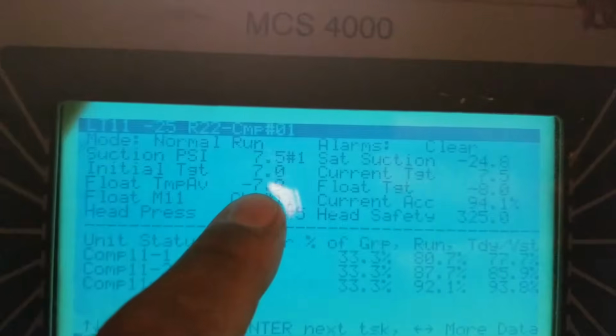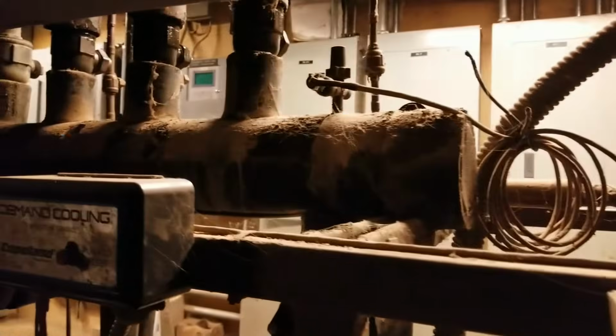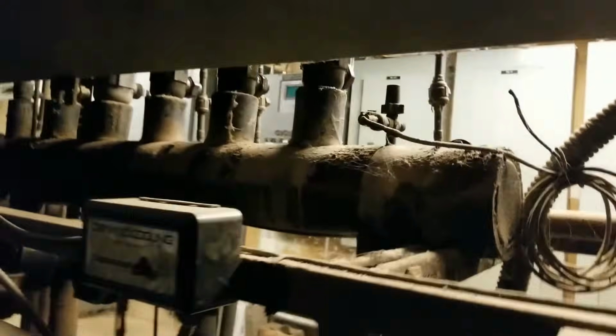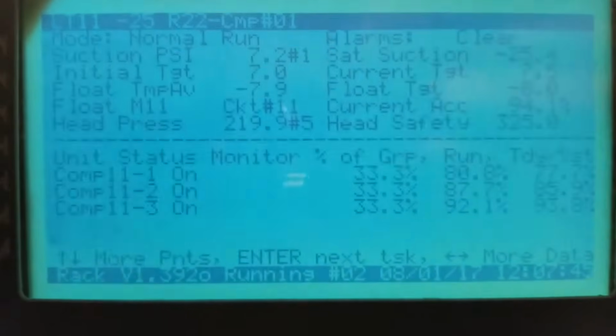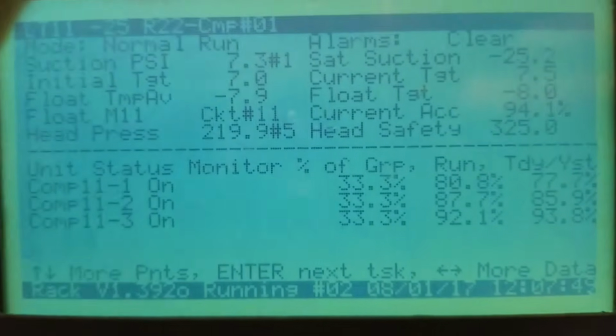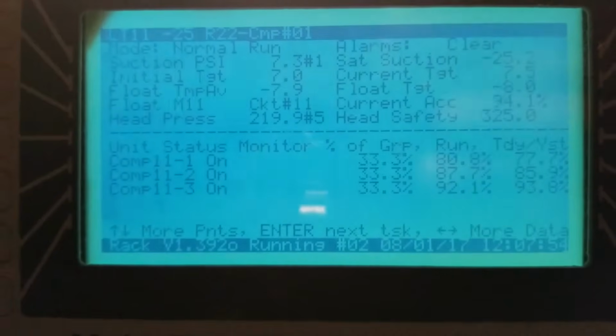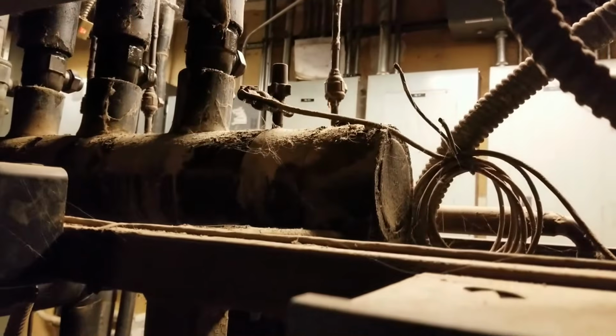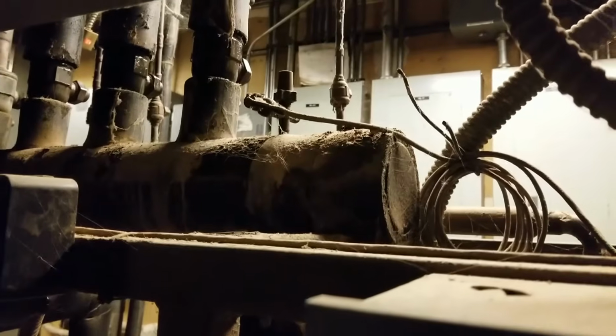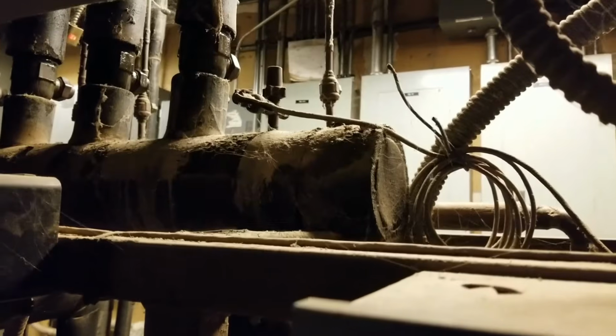So these cases do not have thermostats inside of them or an EPR inside of them. It's being controlled off the suction header, which is right here. That transducer right there is actually controlling your temperature for the frozen food cases or the ice cream cases. So if it's not making temperature or suction, then something's wrong. A lot of times, it's a calibration issue. Either the transducer right there is out of calibration, so that'll throw the temperature either too cold or too warm. But if the transducer is calibrated correctly and it's still not reaching temp, then most likely it's your temperature at your cases.